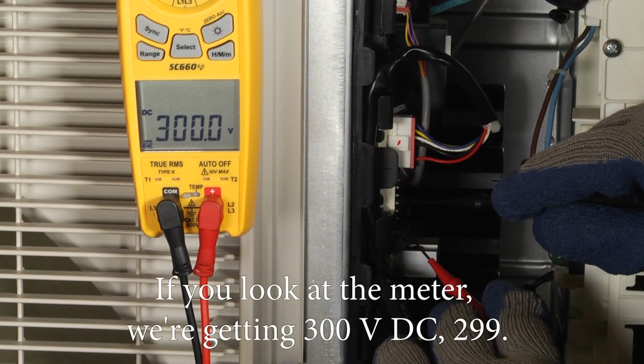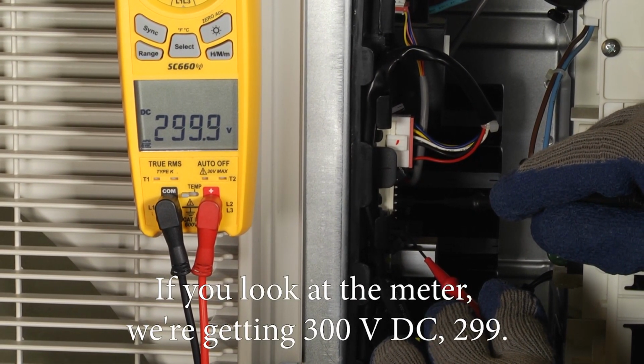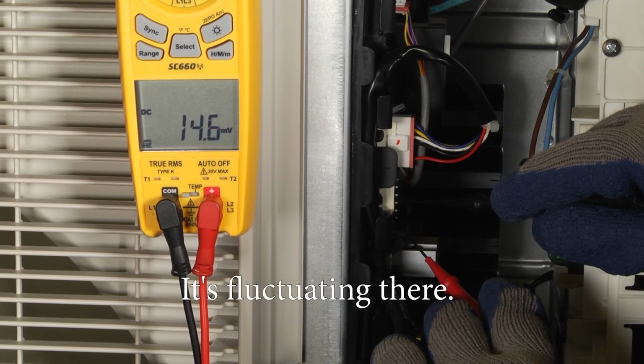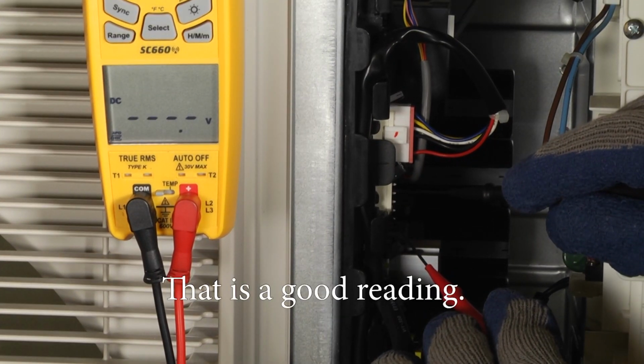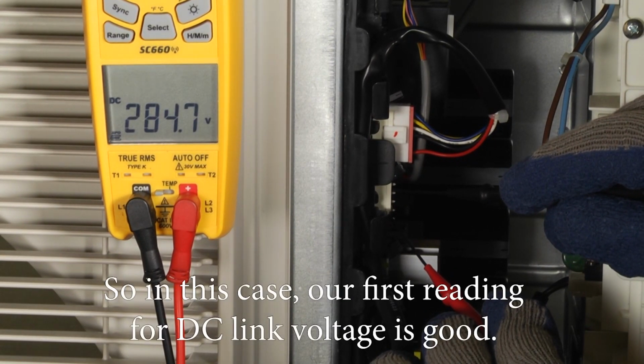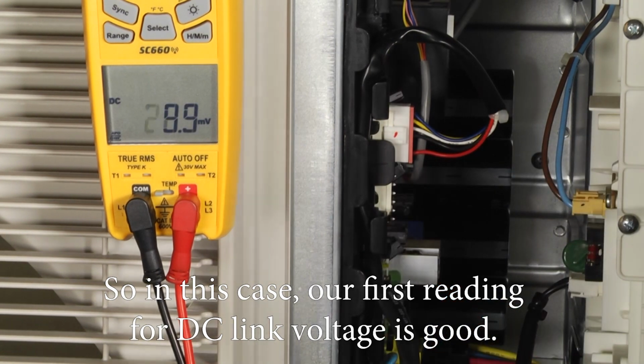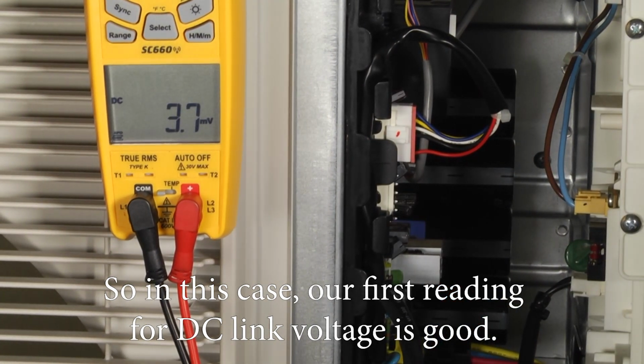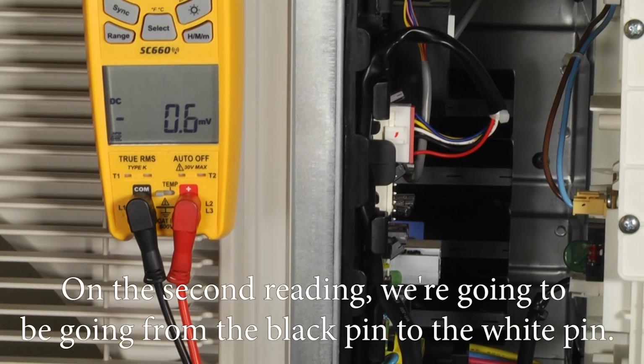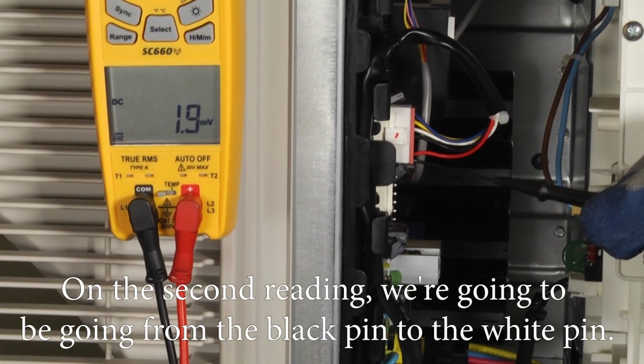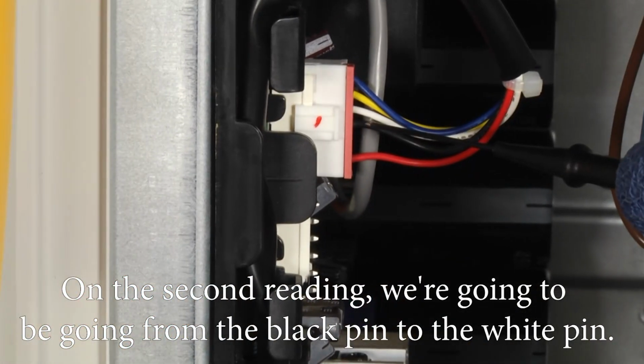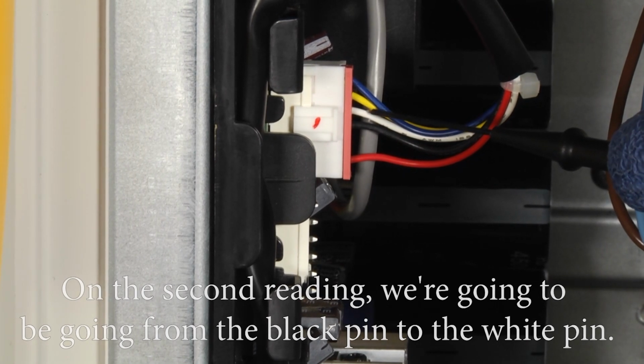So if you look at the meter, we're getting 300 volts DC, 299. It's kind of fluctuating there. That is a good reading. So in this case, our first reading for DC link voltage is good. On the second reading, we're going to be going from the black pin to the white pin.